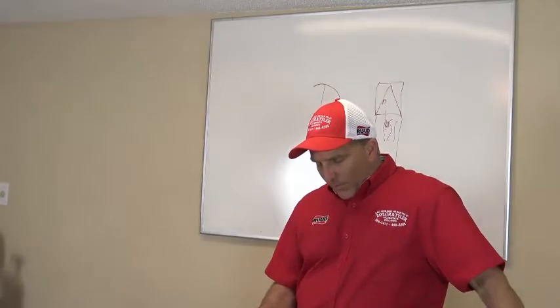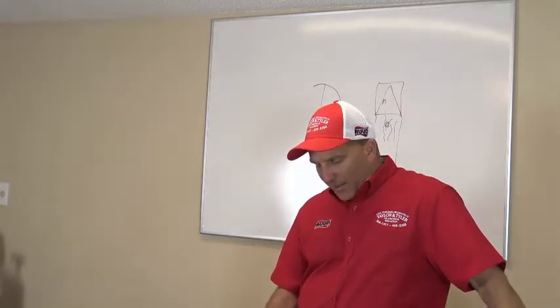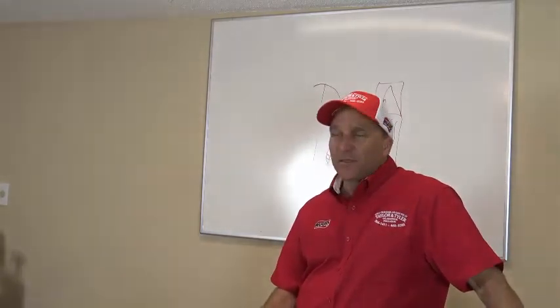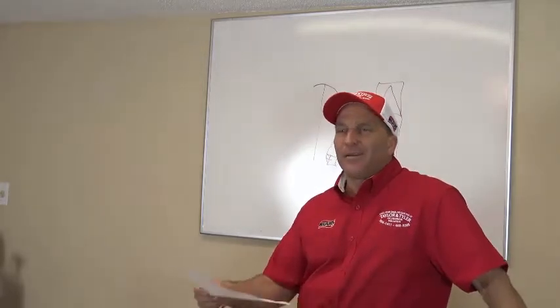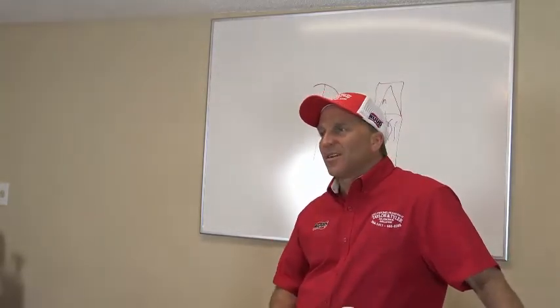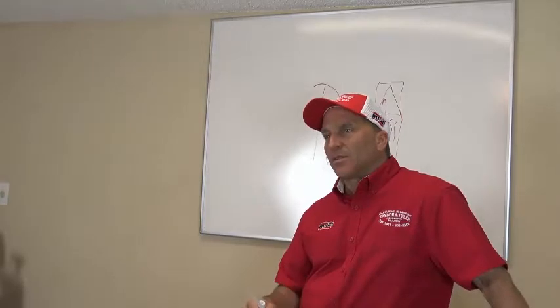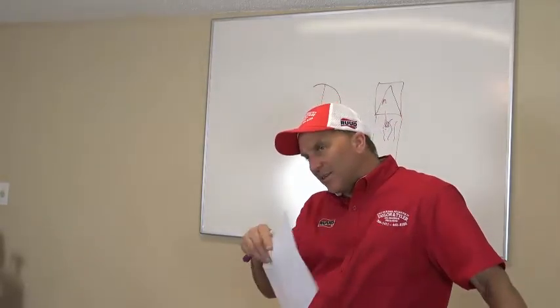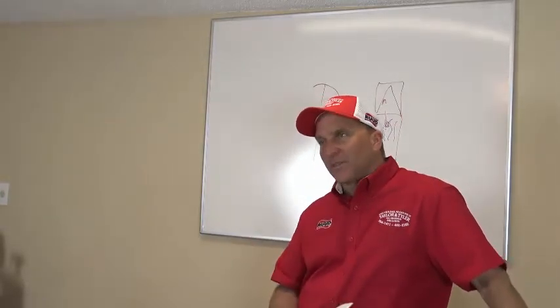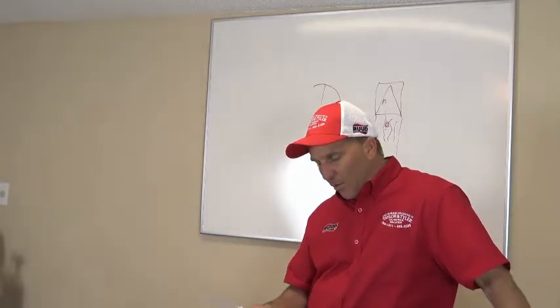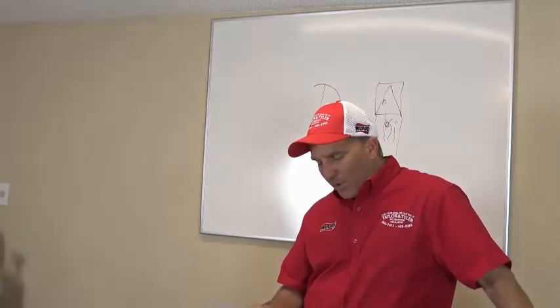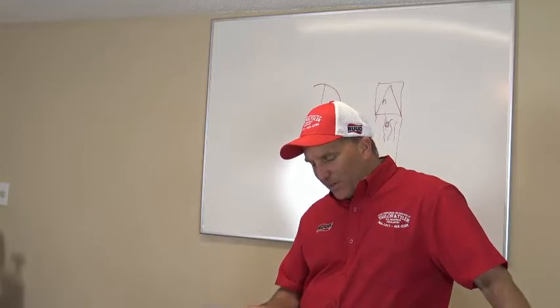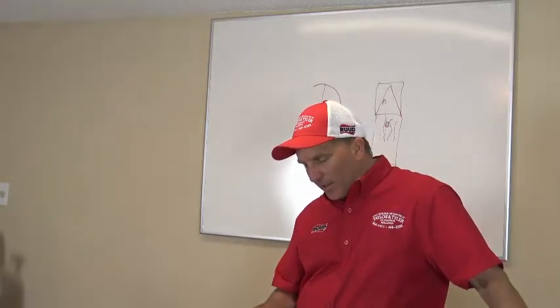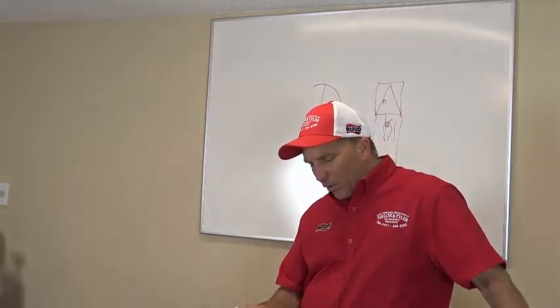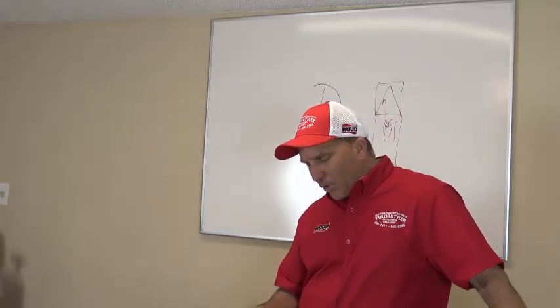All right, I want to know if your coil pan is okay or is it clogged or rusted. Sometimes you got a vertical system and that coil pan is all rusted and clogged up. Sometimes on a horizontal system, you can open up the side of that system and see it all clogged and gook all up inside there, especially if you got a dirty evaporator coil. Okay? I want to know if you got a TXV or a piston, and I want to know if it's okay, restricted or not insulated, or if it's the wrong size piston, or if it's restricted.